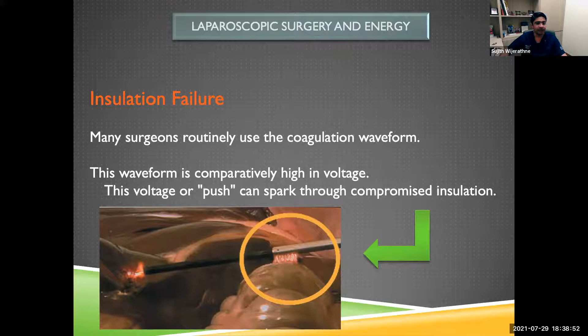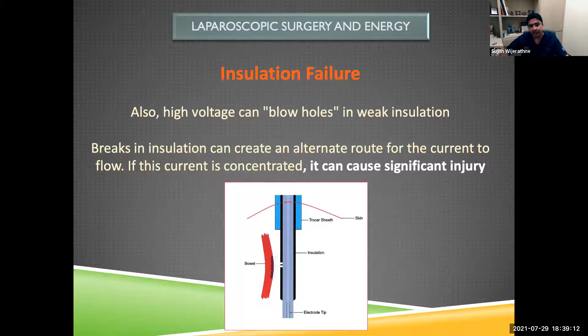Also, usage of high voltage during usage of monopolar instruments weakens the insulation. So breaks in insulation can create an alternate route for the current to flow. And if this current is concentrated, as I told you earlier, it can cause significant injury.